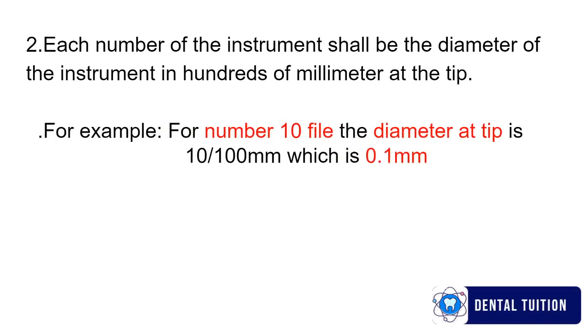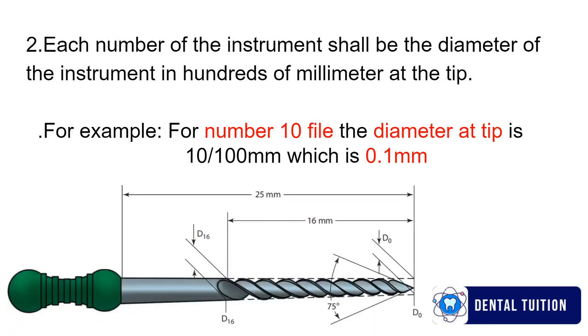Now coming towards another recommendation, each number of the instrument shall be the diameter of the instrument in hundreds of millimeter at the tip of the instrument. For example, in number 10 file the diameter at the tip is 10 by 100 which is 0.1 millimeter. In the given figure you can appreciate the tip of the instrument.